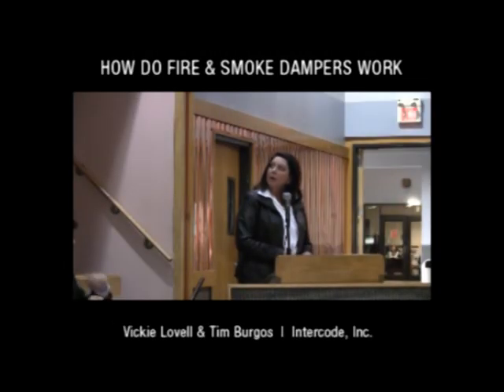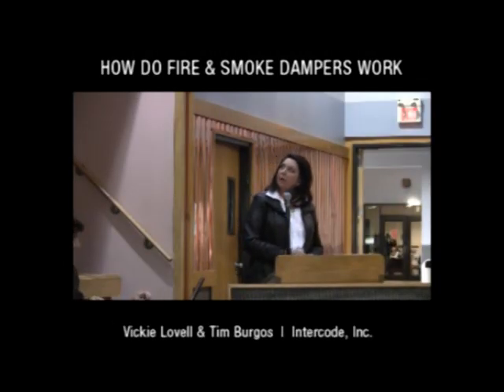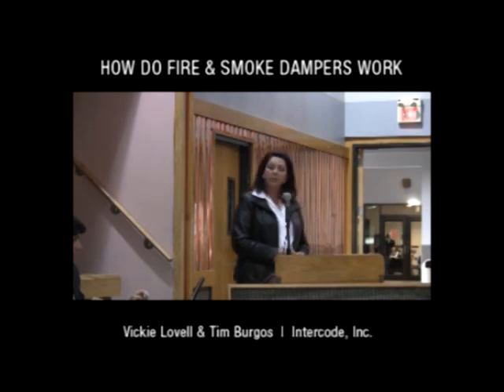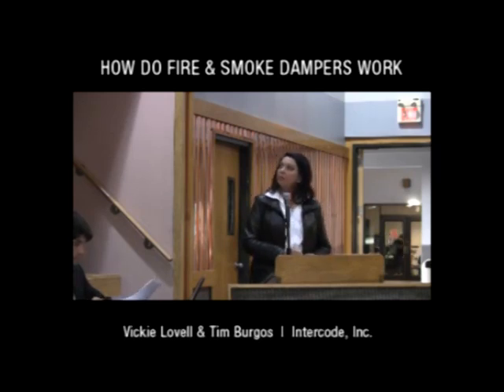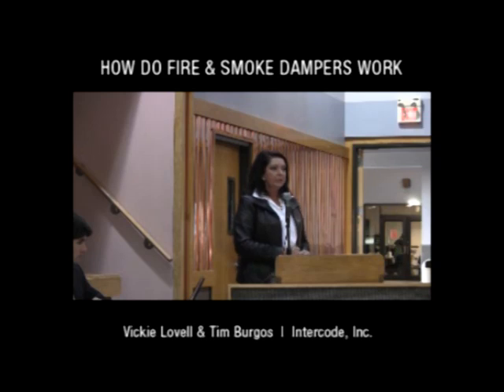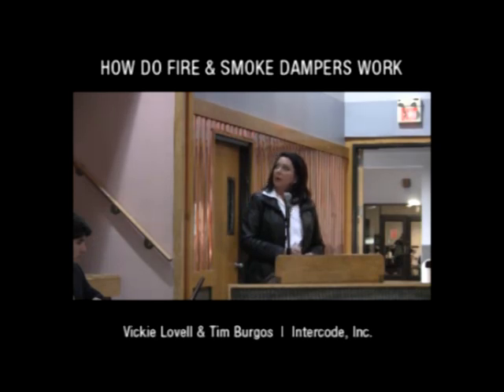This morning, we'd just like to refresh you on what a properly functioning damper is supposed to do. Now, these are life safety dampers. These are specifically fire dampers. In some cases, we'll be talking about smoke dampers, but the intent of it is to control the migration of fire and the byproducts of fire through the duct system of the HVAC system.